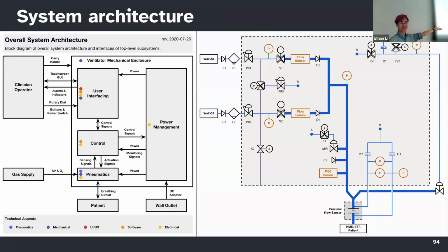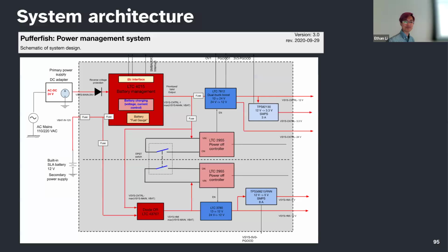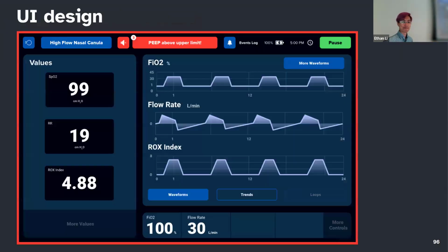For example, the pneumatic systems, which you see on the right, had to implement appropriate airflow control and sensing for a variety of ventilation modes and safety risk conditions, as well as mitigations for certain potential failure modes of the system. These requirements in turn generated many requirements for the software that would control our pneumatic sensors and actuators. Similarly, our electrical systems also had to manage safety risks. For example, because our device was in control of every single patient breath, we had to properly mitigate loss of external power. These kinds of requirements created additional requirements for the software.